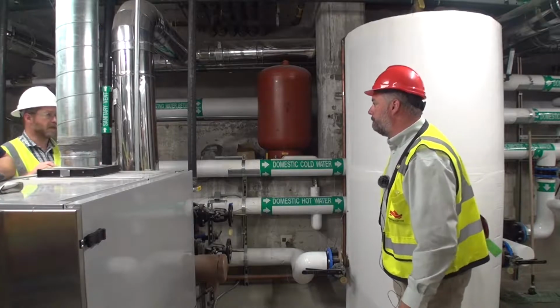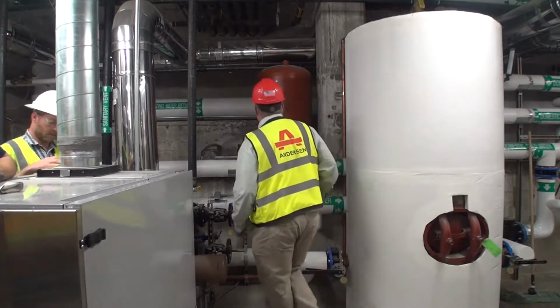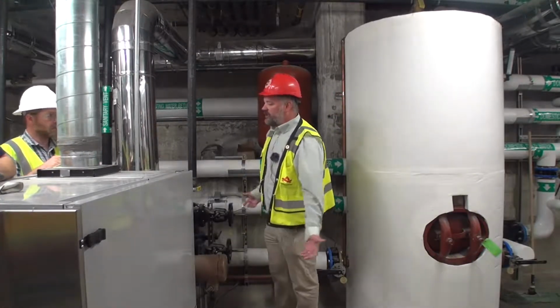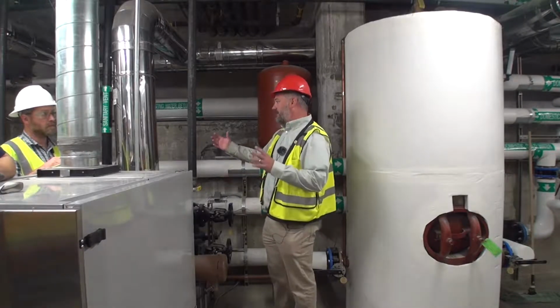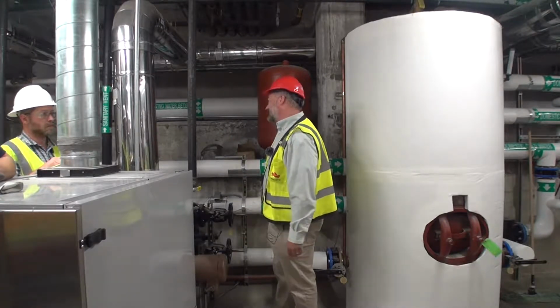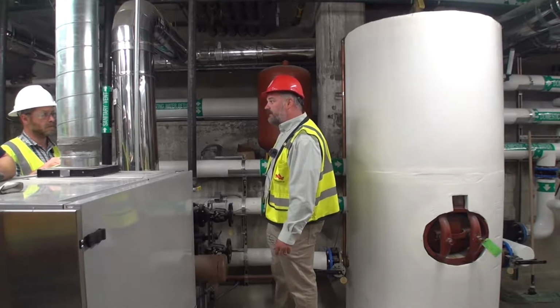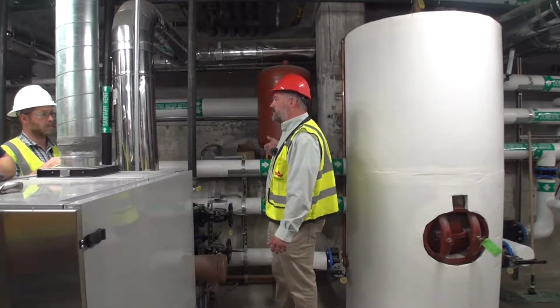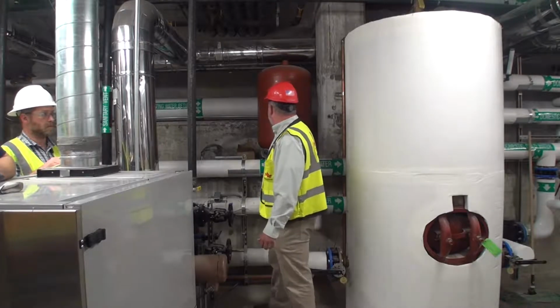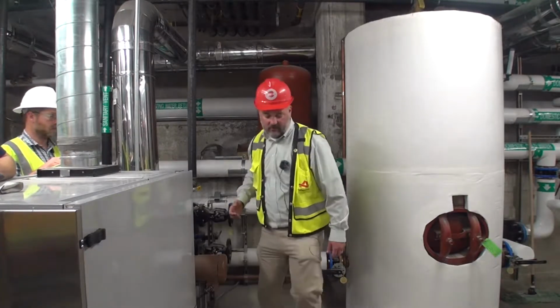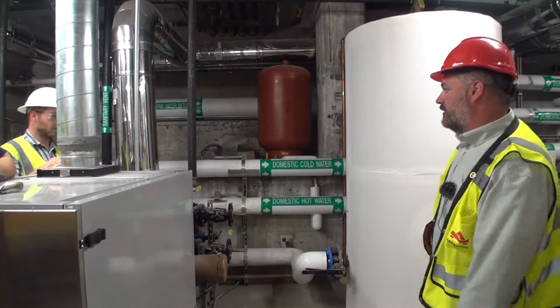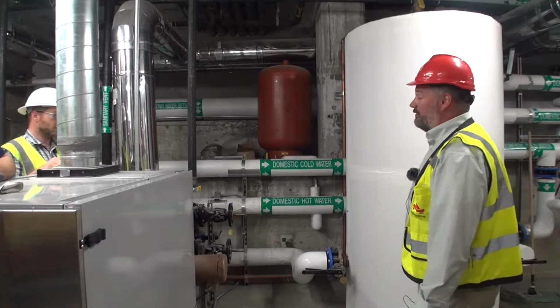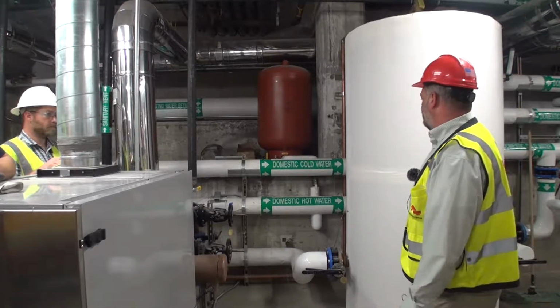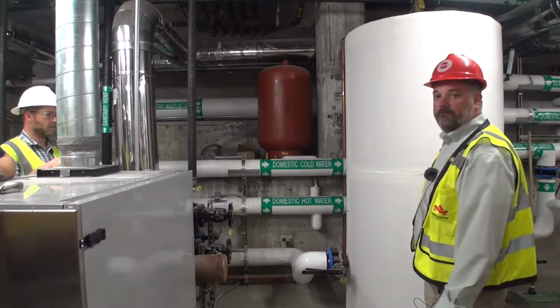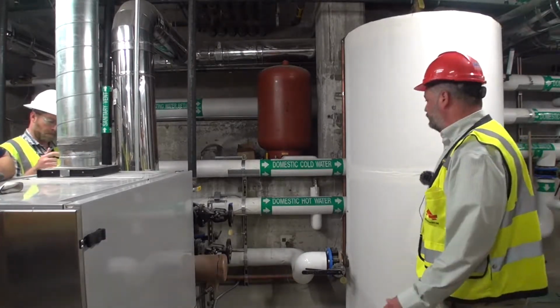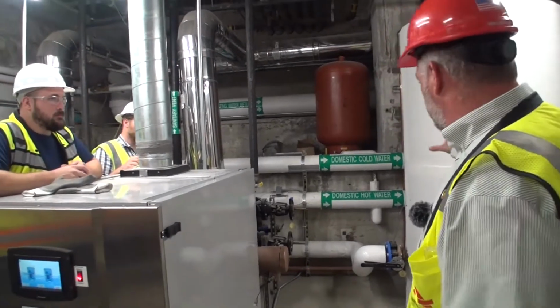What's the pressurization on that bladder? It depends on what they set it for. Your system pressure traditionally is 70 psi in the system. Lots of your tanks are coming shipped at 40 psi. Some are even lower, and you pressurize them up. We suggest that a lot of times you pressurize it to around 5 psi below what the system pressure is, to make sure. I don't know off the top what that one is without going back to our service agent. Okay, that's kind of just a real generic overview.